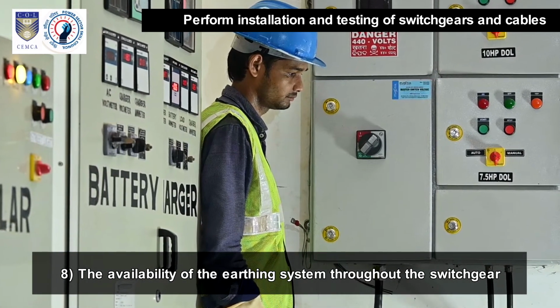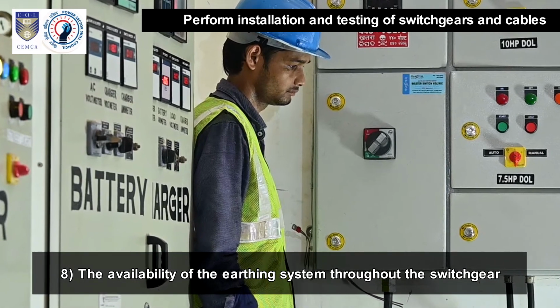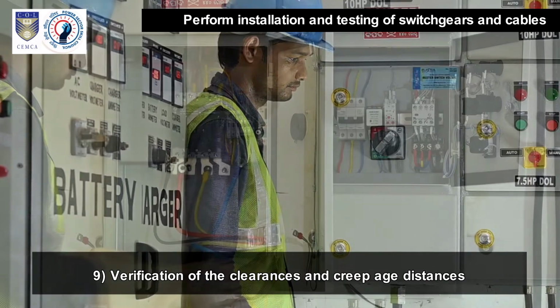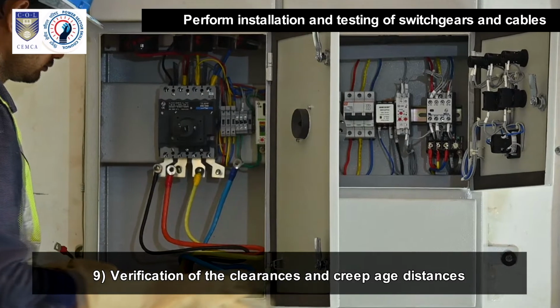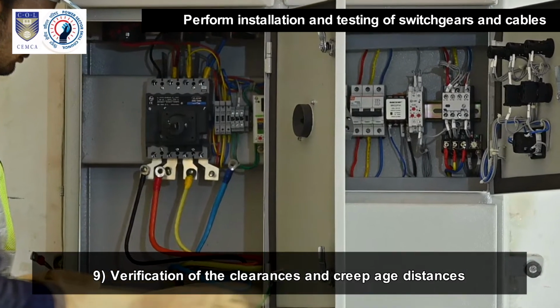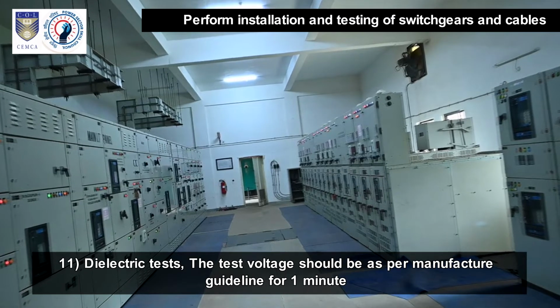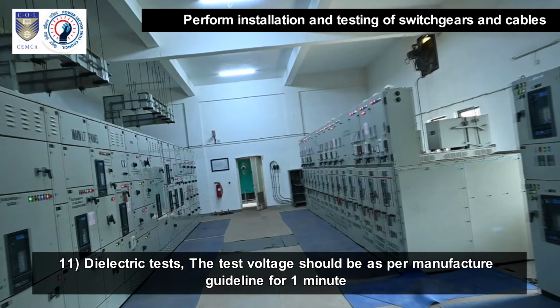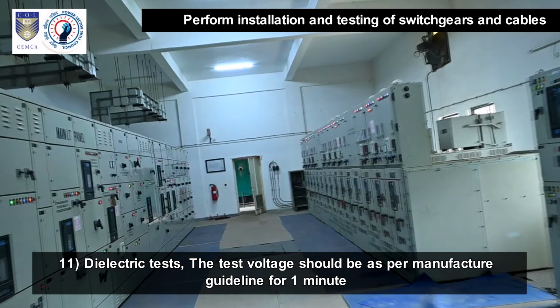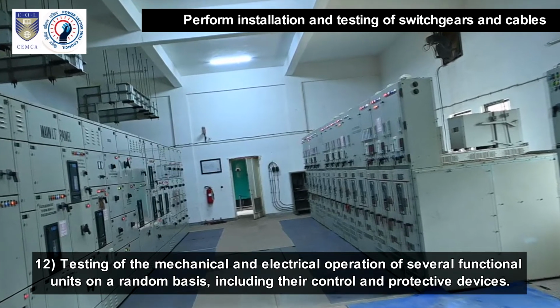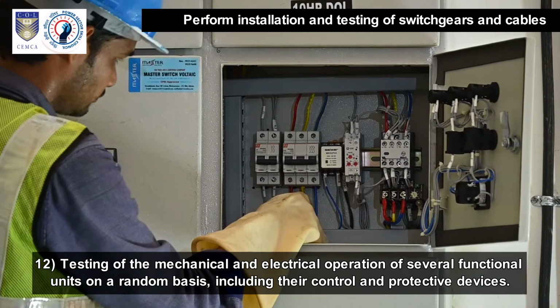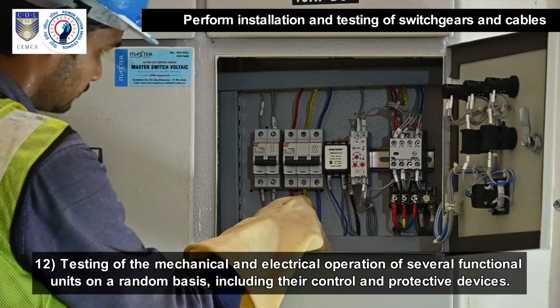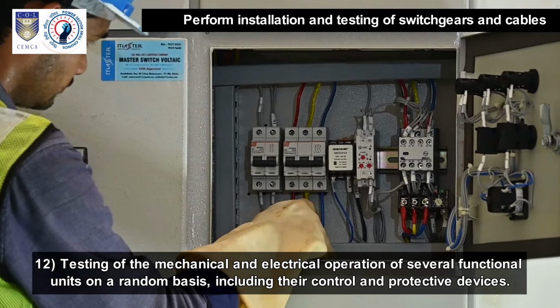8. The availability of the earthing system throughout the switchgear. 9. Verification of the clearances and creepage distances. 10. Verification of mechanical operations. 11. Dielectric tests. The test voltage should be as per manufacturer guideline for 1 minute. 12. Testing of the mechanical and electrical operation of several functional units on a random basis, including the control and protective devices.